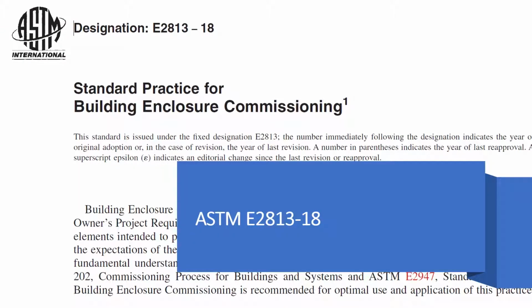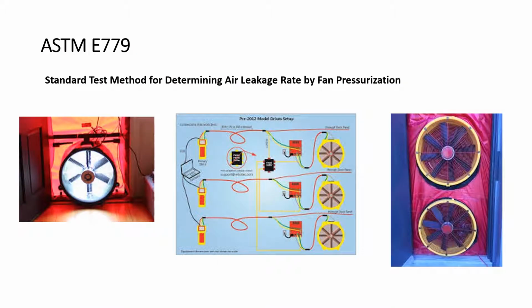As I mentioned, NIBS, the National Institute of Building Science, is no longer maintaining this and has turned the upgrading and care and management of this over to ASTM. So that's just a copy of the ASTM document. ASTM E779, standard test method for determining air leakage by fan pressurization. Obviously, we've got the fans shown there in the picture, and that is how we determined, in this case, whole building air leakage. You can see the two fans, and in the middle is a fan array to control multiple fans. In all of our tests, we used two fans. We did not have to go to three.